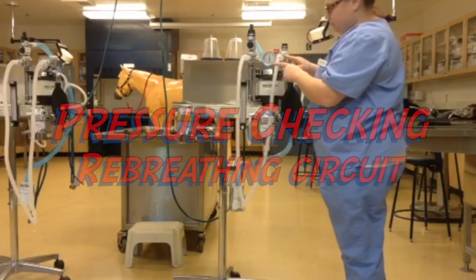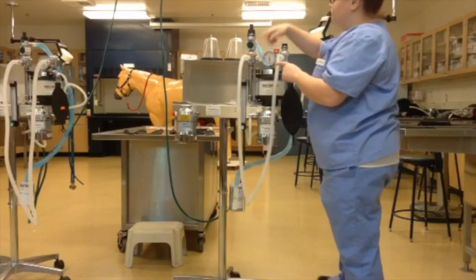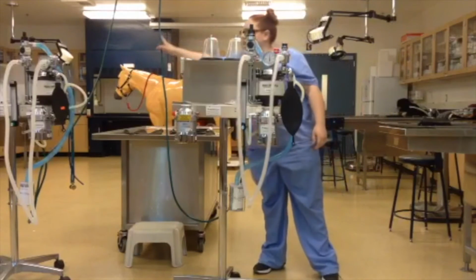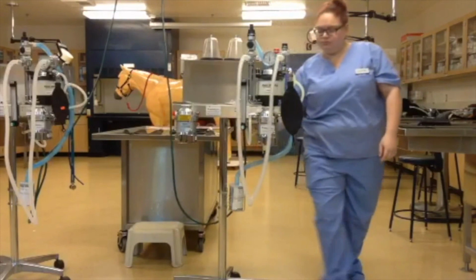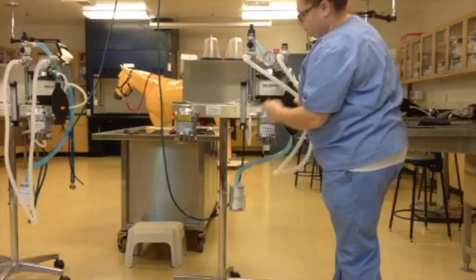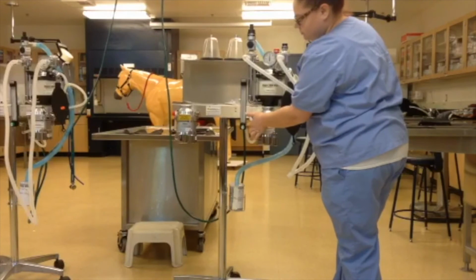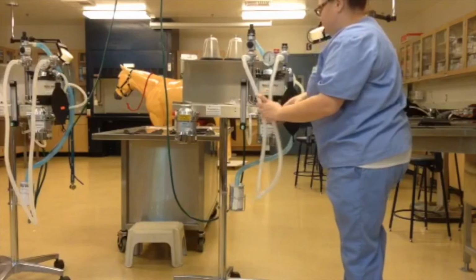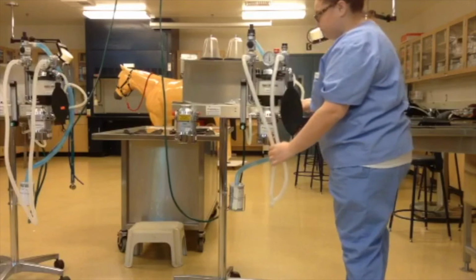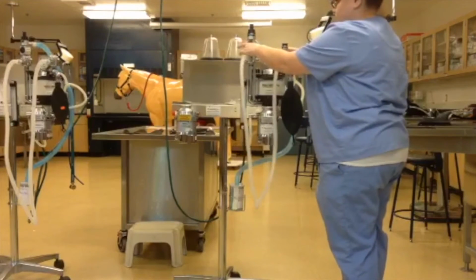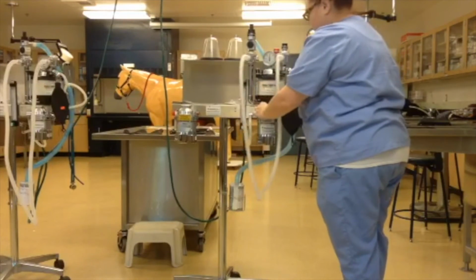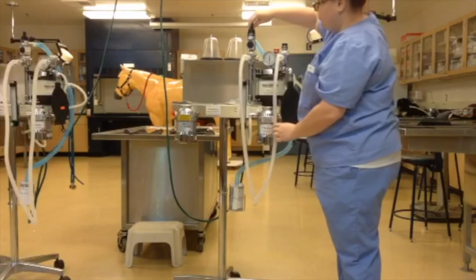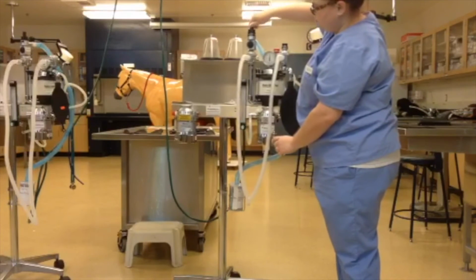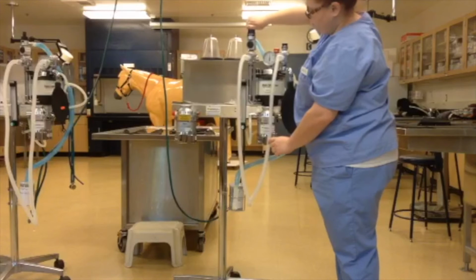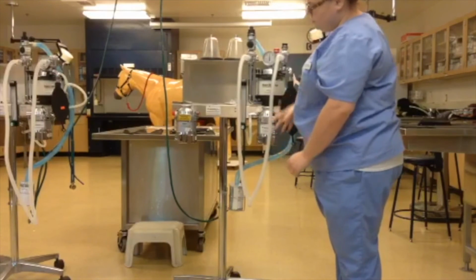Now we'll be completing a pressure check. We're checking that we have our inhalation and exhalation tubes connected. Our oxygen is connected to the flow meter and the oxygen valve. That is what we'll be mainly using, the oxygen valve. And we're going to make sure that we have our reservoir bag, and that everything is secure and tight and everything is connected. We're closing off the pop-off valve to the right, righty-tighty, lefty-loosey.